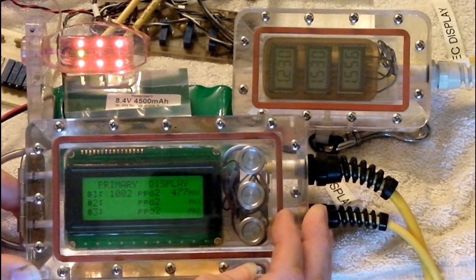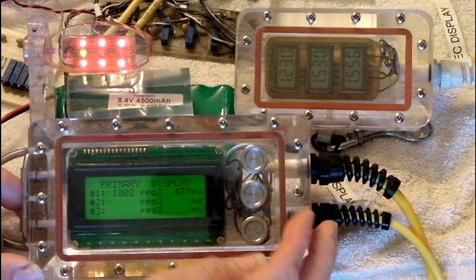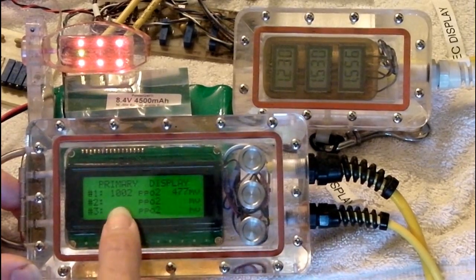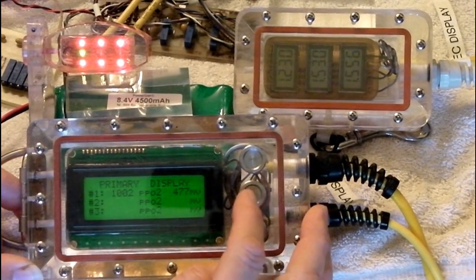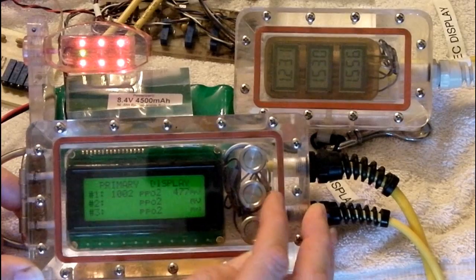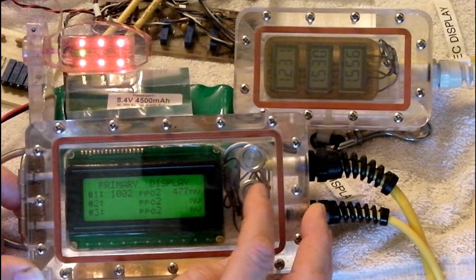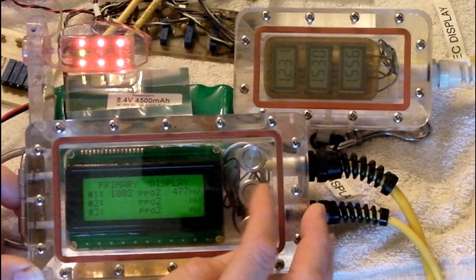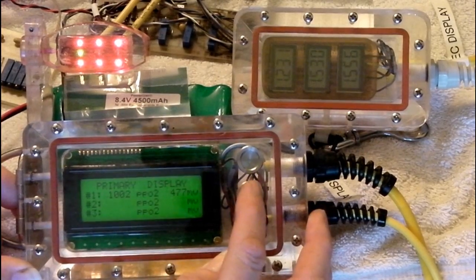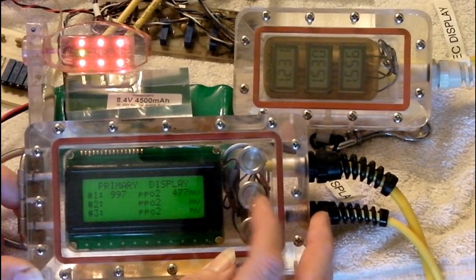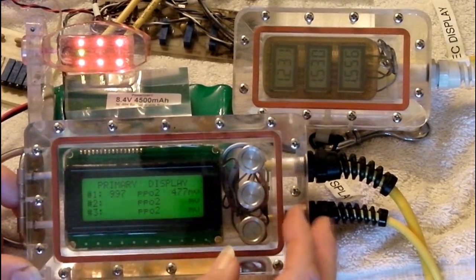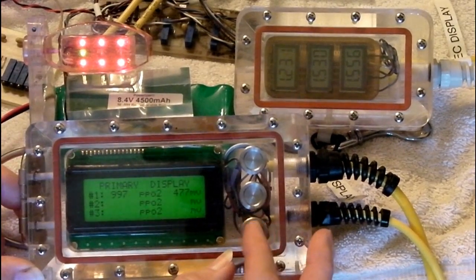To calibrate, you need to know what your known gas is in the loop, and you calibrate your PO2 display until it matches. So let's assume we have something on the order of about 99%, because that's pretty accurate for what we can get from flushes. We'll drop this down, and we're at 99.7. That's a good place to start.